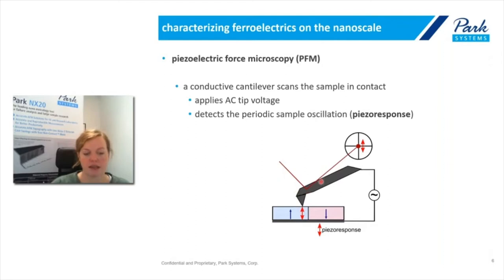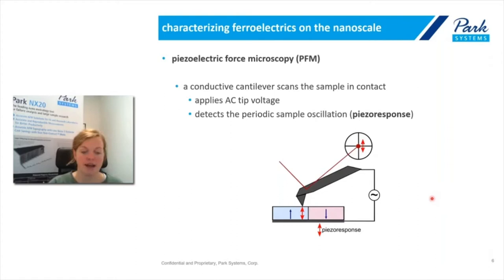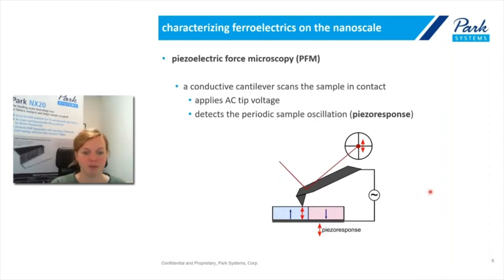We can see this piezo response here in red. The sample oscillation is detected by the beam deflection and then detected on the photodiode. The sample signals we get are: first, the phase of this piezo response compared to the excitation signal, which gives us information on domain orientation; and second, the amplitude of the piezo response, which carries information on the position of domain walls — whenever we reach a domain wall, the amplitude gets minimal.